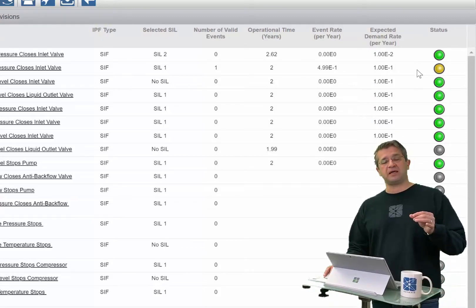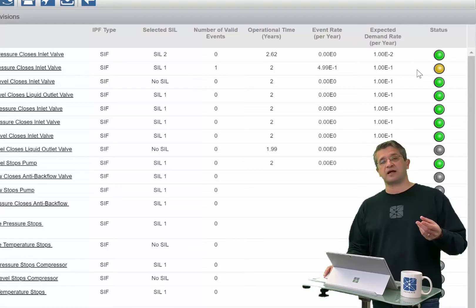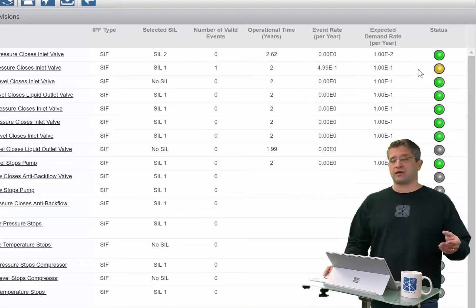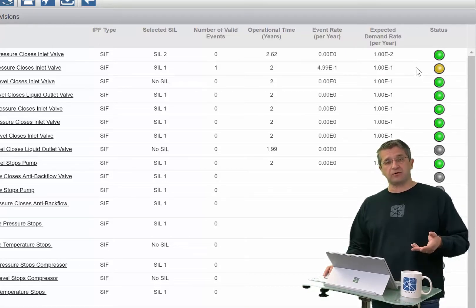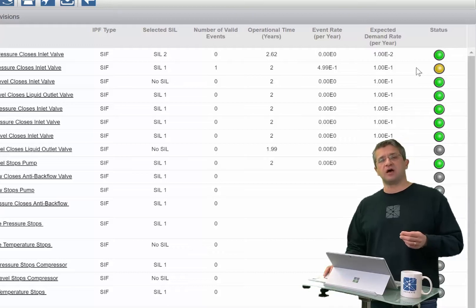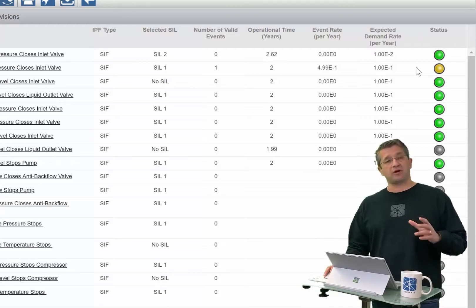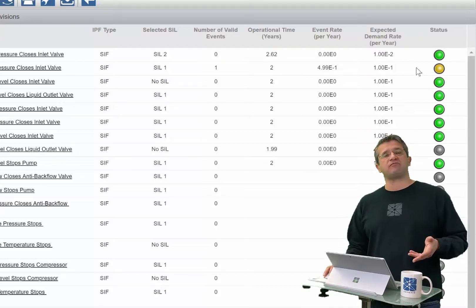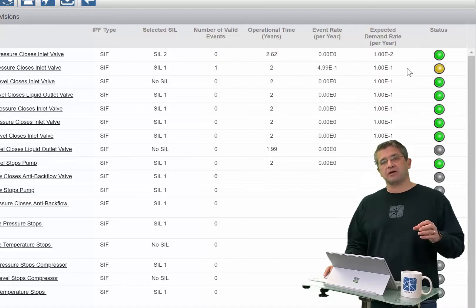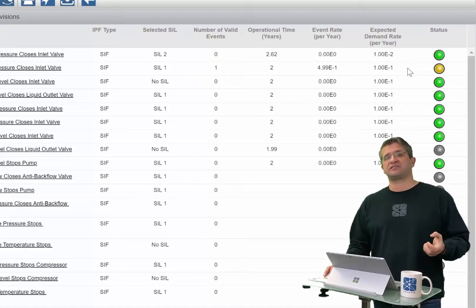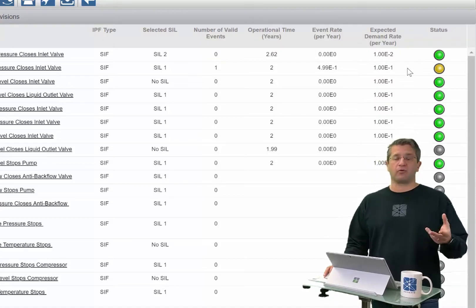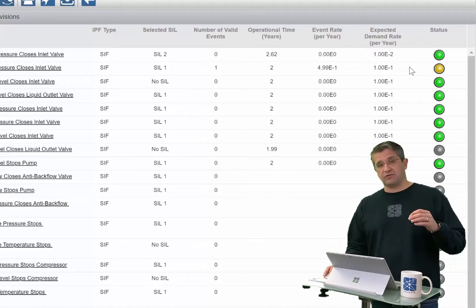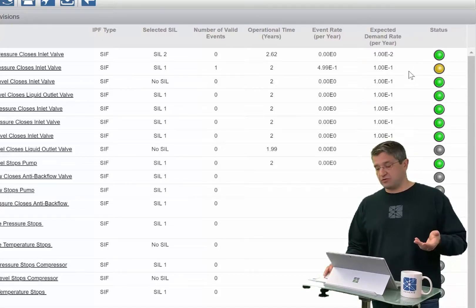Yellow events should possibly be reconsidered during risk analysis or during periodic review of safety performance audits to determine whether more safeguarding might be appropriate, because the safeguards are activating much more frequently than the risk analysis expected them to.